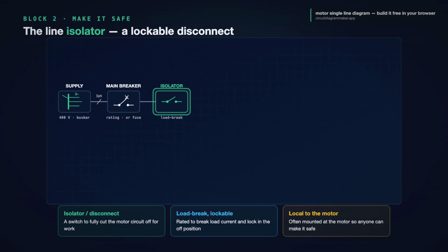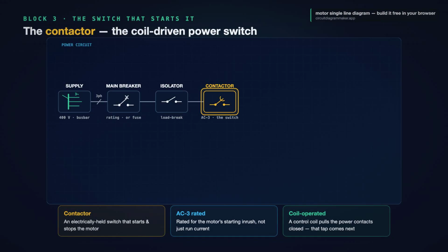Block 3, and the heart of the whole thing, the contactor. The contactor is an electrically operated switch, the device that actually starts and stops the motor. On the single-line diagram, it is drawn as a switch with a small arc on the moving contact, and that arc is how you tell a contactor from a plain switch at a glance. Two things matter here. It is AC3 rated, which means it is built for the heavy inrush current a motor pulls at start, not just the steady run current. And it is coil-operated. A control coil pulls the power contacts closed. That coil is a whole little circuit of its own, and we will tap it off in a moment. For now, contactor, the switch that makes the motor go.